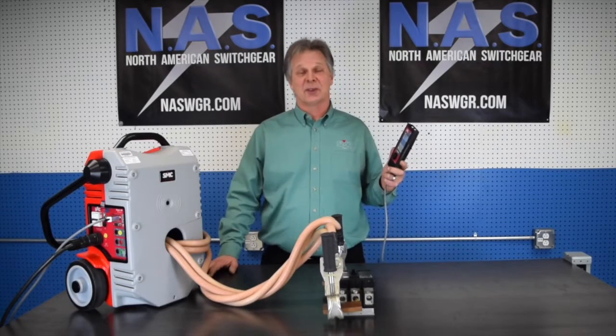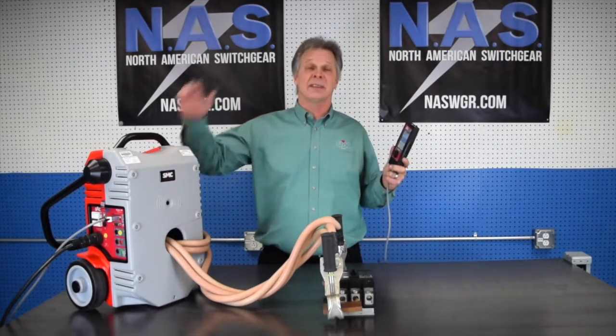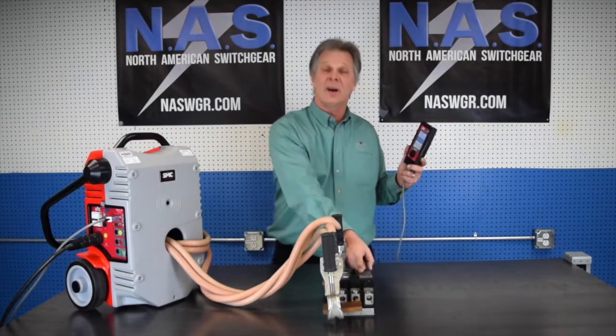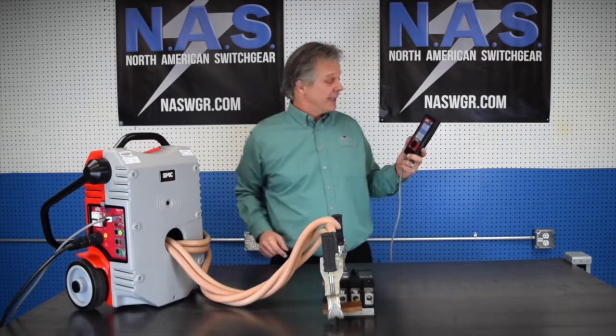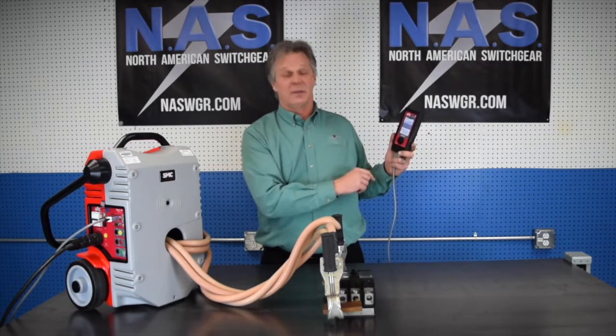Hi folks, John Musgrove from SMC at North American Switchgear, and today we're popping breakers. I've got a 225 amp breaker, and we're going to do an instantaneous test at 2,250 amps.